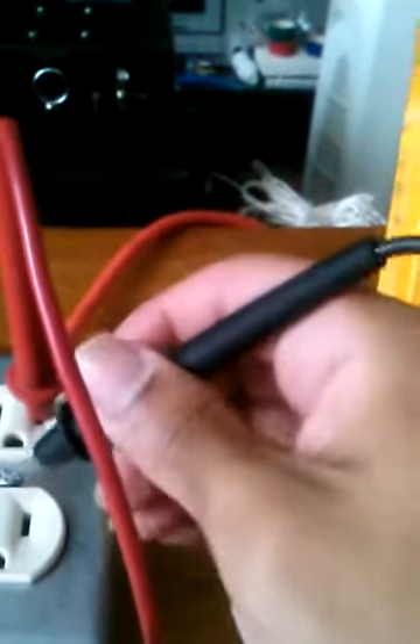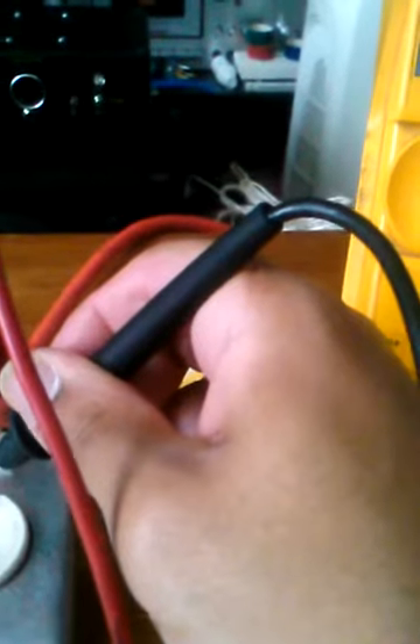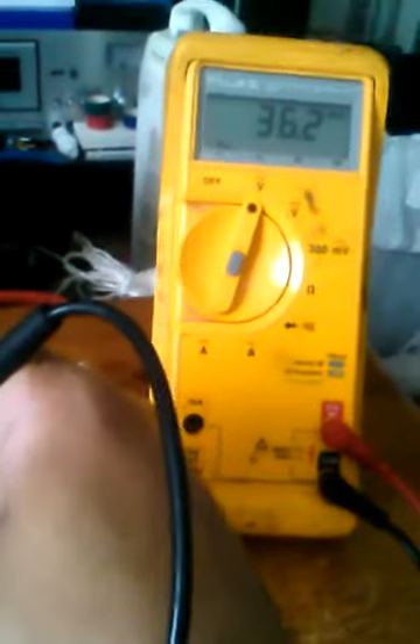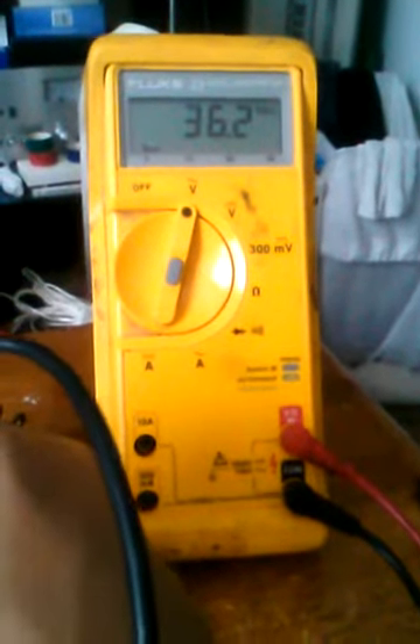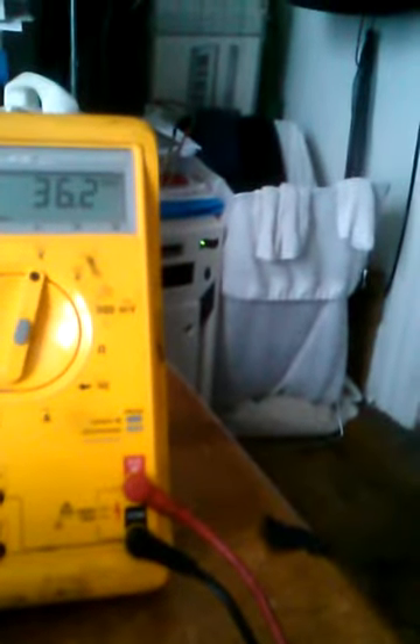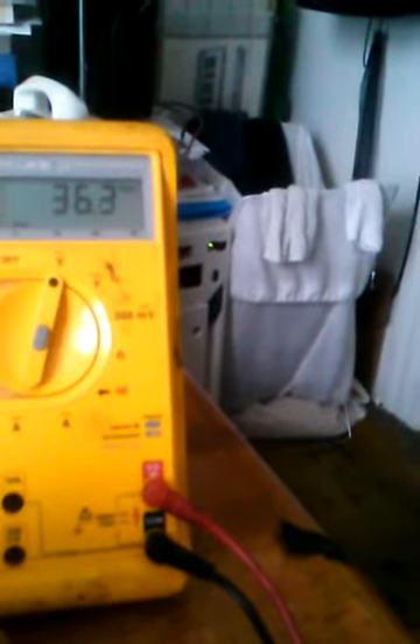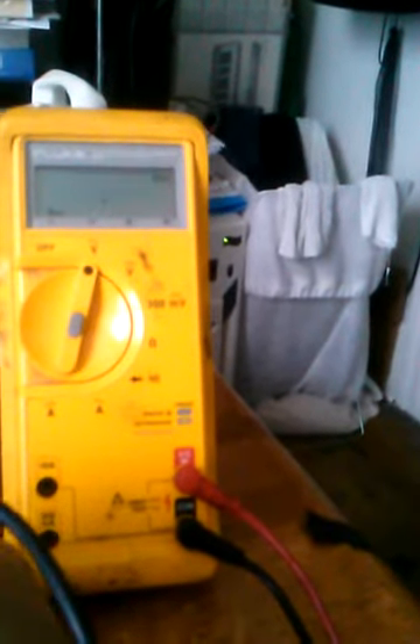Now we're going to plug the probe back into the hot side of the outlet again, and then test the ground. I don't know why it's coming in at 36, but it's understood that this circuit is open. The ground is open as indicated on the receptacle tester here.